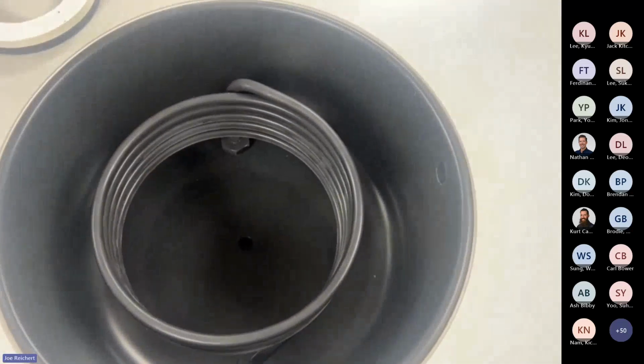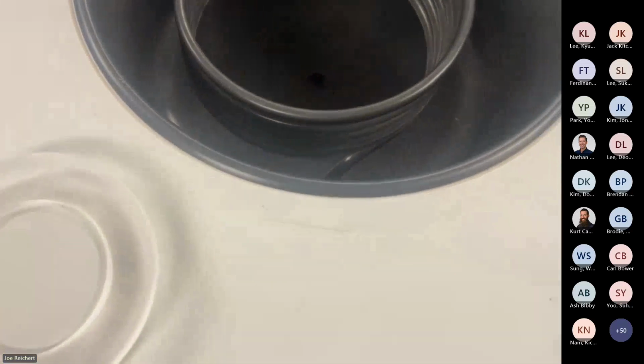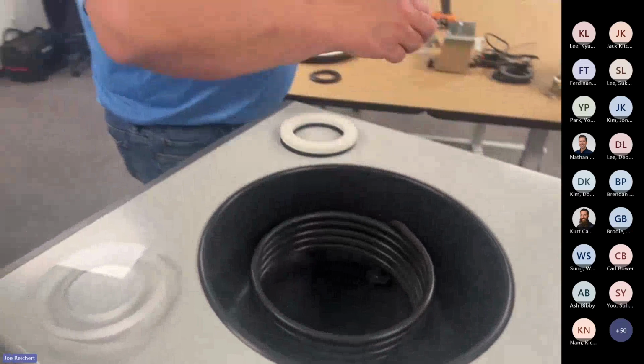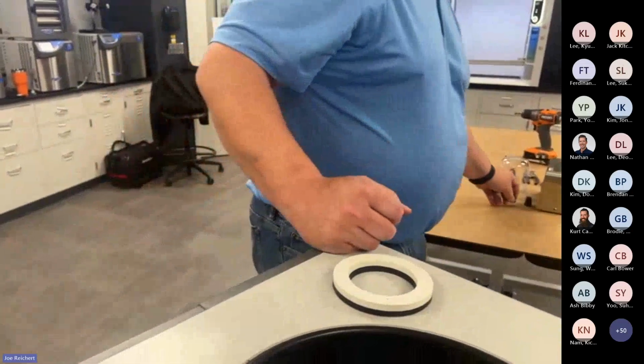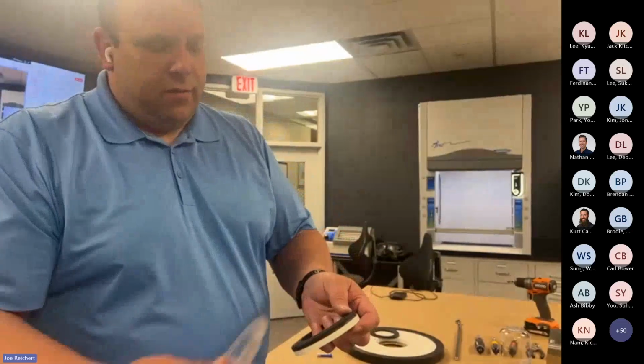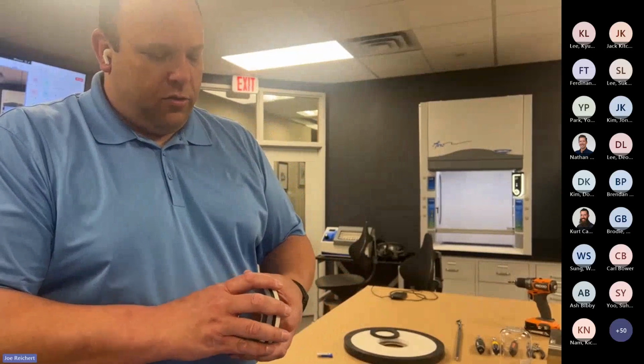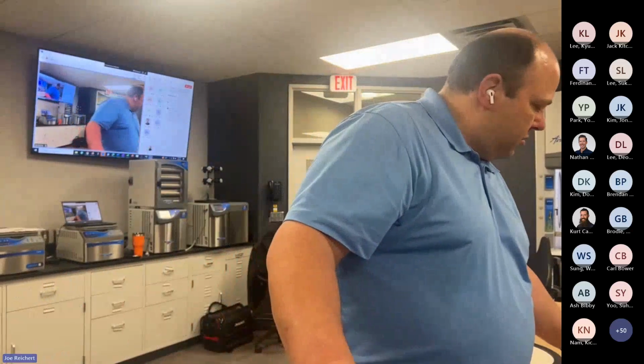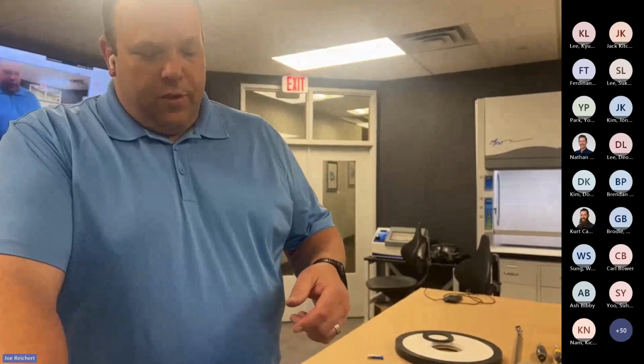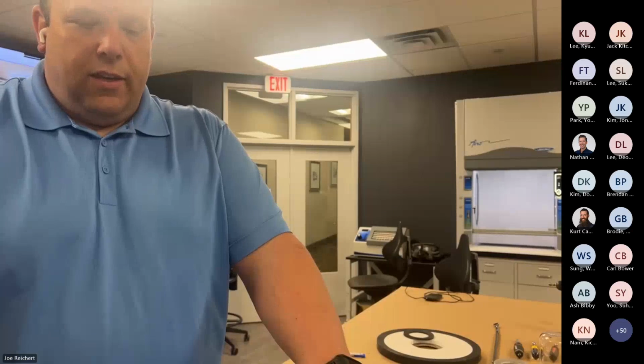Now, something I usually like to tell people on freeze dryers and tell all of our service engineers is that a CentriVap or a freeze dryer only do two jobs. They are supposed to get cold or heat, like in a CentriVap or on shelves of an accessory, and they're supposed to hold a deep vacuum. If the machine does both of those, then it is doing its job. If a sample is not drying properly, there's some other force that is making it not dry.